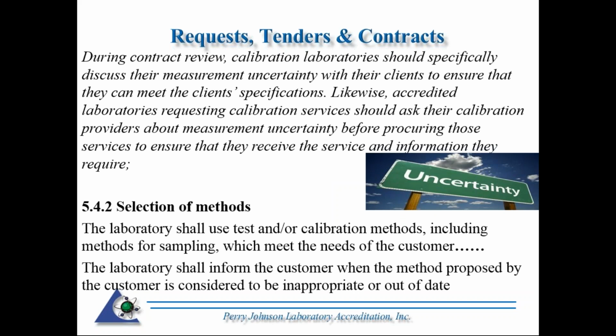Okay, once again, during contract review, calibration labs should specifically discuss their measurement uncertainty with their clients to ensure that they can meet the client's specification. Likewise, accredited labs requesting calibration should ask their calibration providers about measurement uncertainty before procuring those services to ensure that they receive the services and information they require.